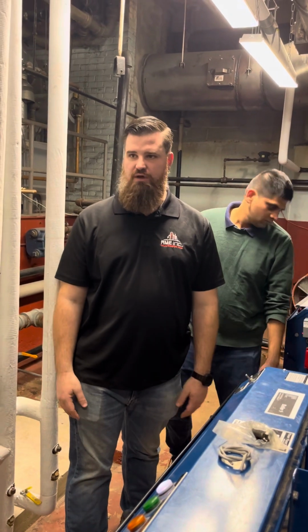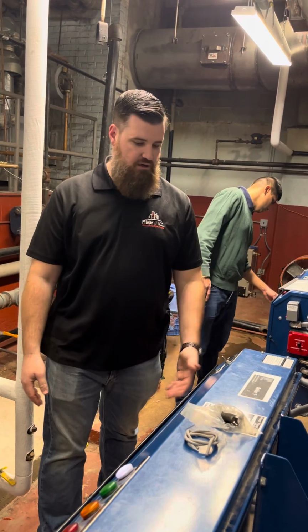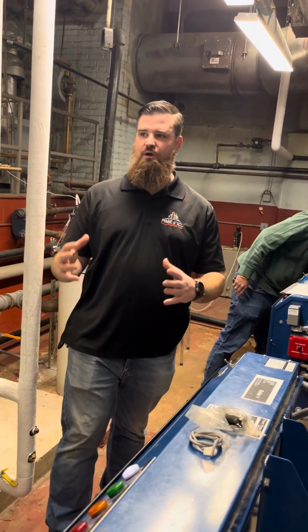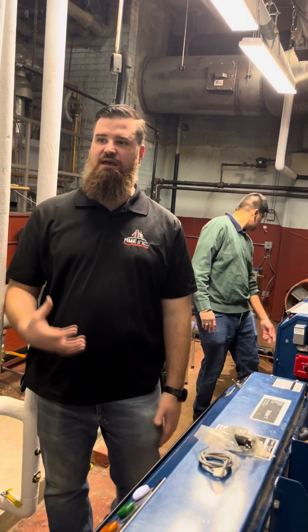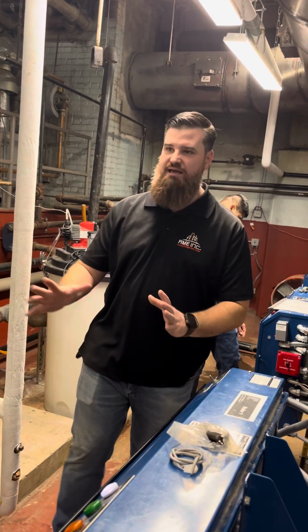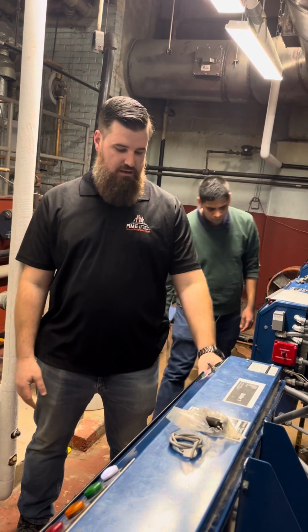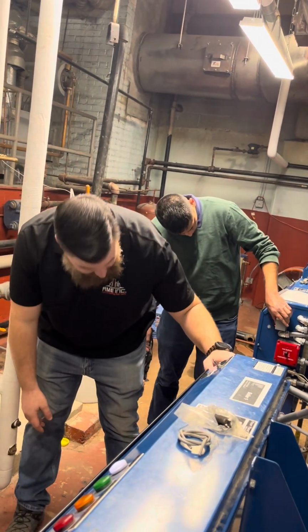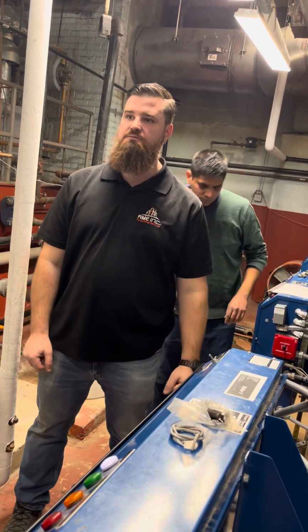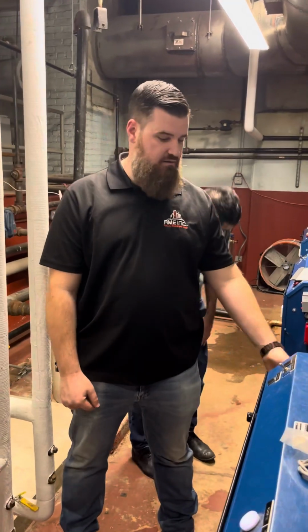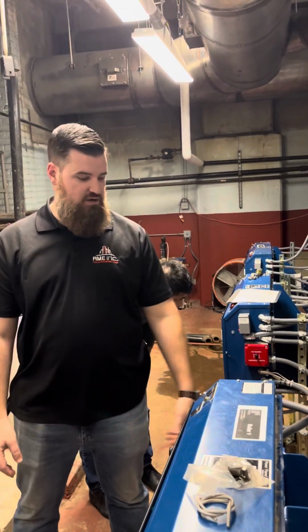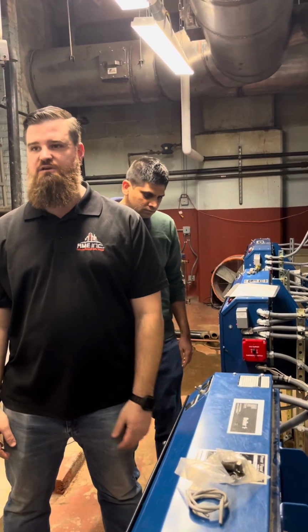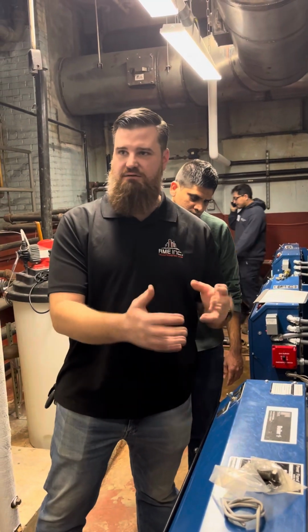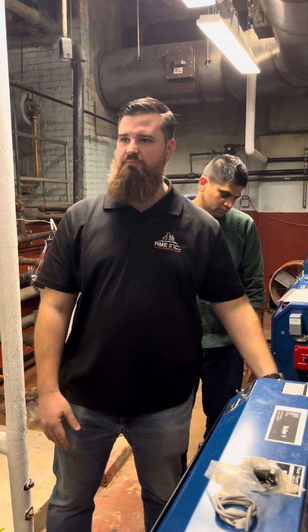Okay? So if you got nothing coming over, my biggest thing, as I told you guys, I want you to have a building automation system. We want everything in auto. You guys got a building to operate, I get it. Do what you got to do. But these should always be in auto. That's my opinion. If you need to shut a boiler down because you need to service it or whatever, your best thing, always come over here, just kill the power. Don't worry about the BMS. Just take the BMS all out by killing the power.